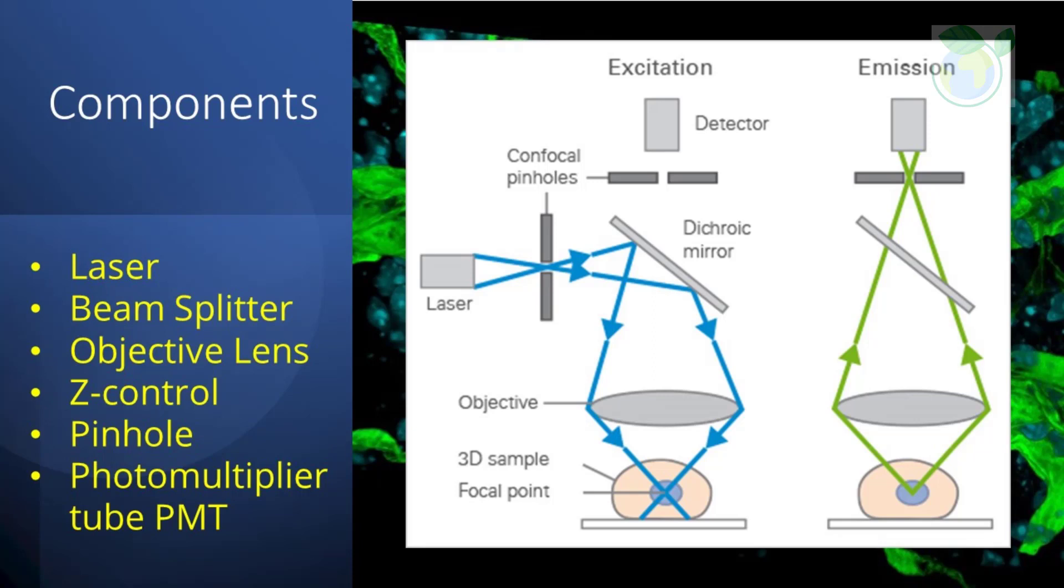In addition, the pinhole is an adjustable iris in the intermediate image plane. It allows exclusion of most of the out-of-focus light from the acquired image and thus provides optical sectioning capacity. It defines the thickness of the optical slice and is dependent on the properties of the objective lens. The pinhole size can be set via the software on your computer and the best trade-off between the efficiency of light collection and optical sectioning is if it is set to one airy unit.